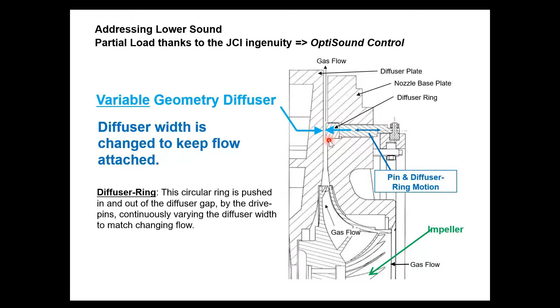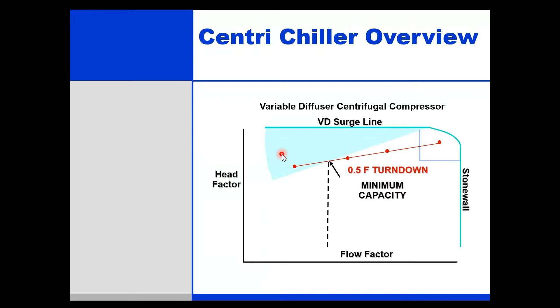So what happens is, the centrifugal chiller, which was earlier maybe stalling at probably 35%, will further unload, because you have shifted the stone wall over here. But it is also important to understand that this is an inefficient process, and as you pinch the particular diffuser and you increase the lift, impart an additional thrust of lift on the refrigerant, the efficiency of the centrifugal chiller also kind of deteriorates. So this is about the variable geometry diffuser, and different people call it differently. Some people call it split ring diffuser, some call it variable geometry diffuser, some call it adjustable diffuser.